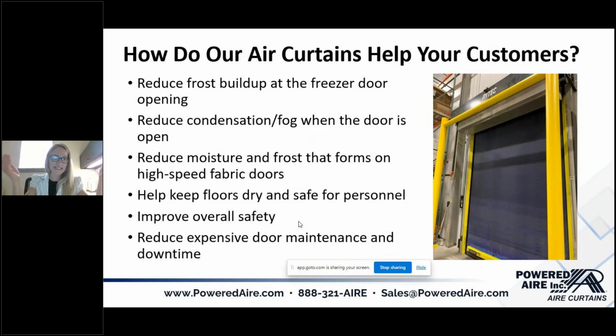With our CAC and FAC, like the video said, they're going to reduce frost buildup in the freezer door opening, reduce condensation and fog, moisture and frost that forms on the high-speed fabric doors. These have very specialized sequence of controls where they're on timers, so even if that door is closed, the unit will come on to clear the door during unused hours. So again, completely different presentation. I'd be more than happy to give it another time, but it is an option that's out there.